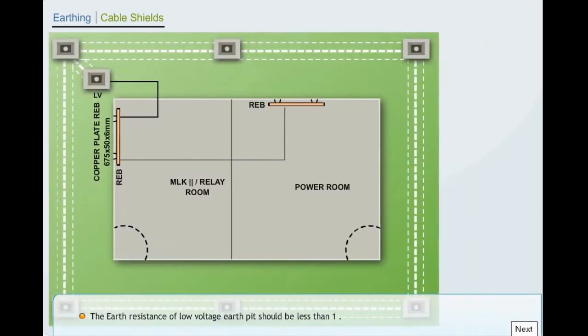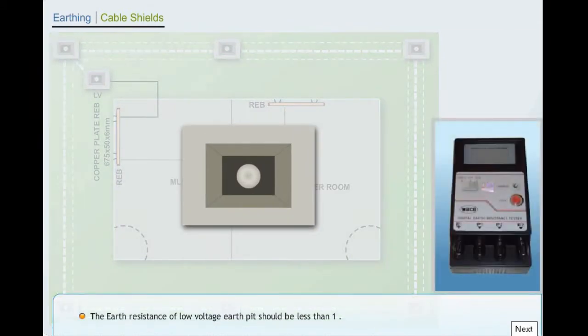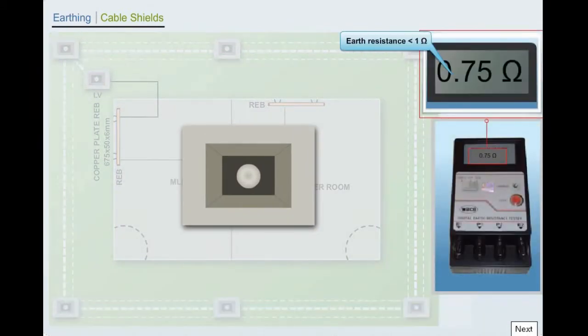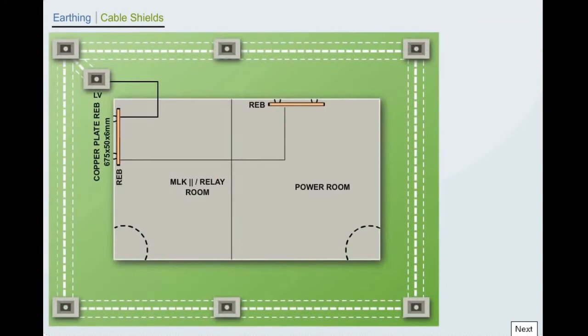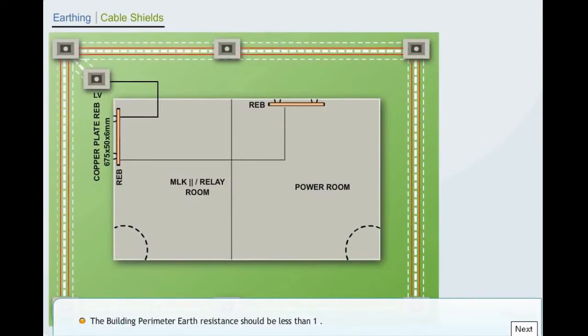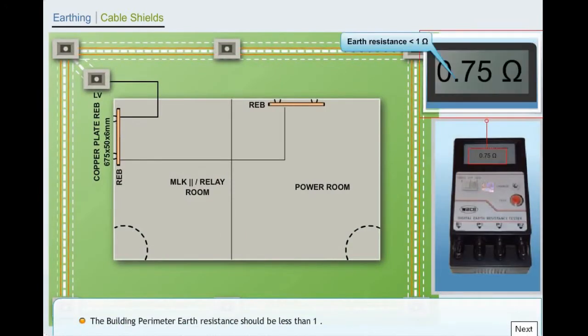The earth resistance of low voltage earth pit should be less than 1 ohm and it should be less than 5 ohms in rocky areas. The building perimeter earth resistance should be less than 1 ohm.